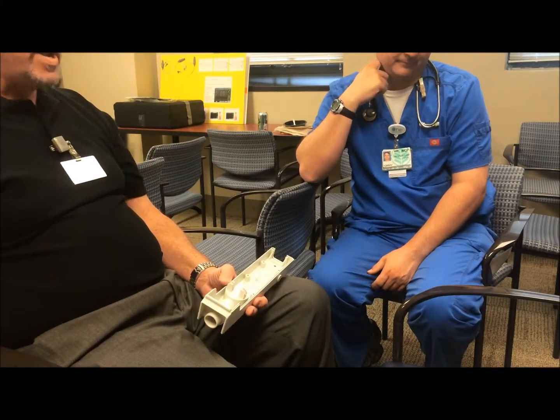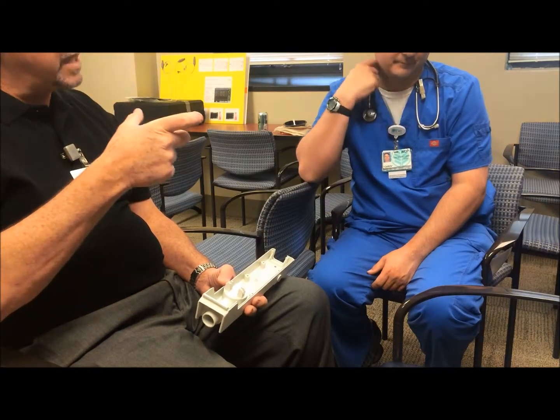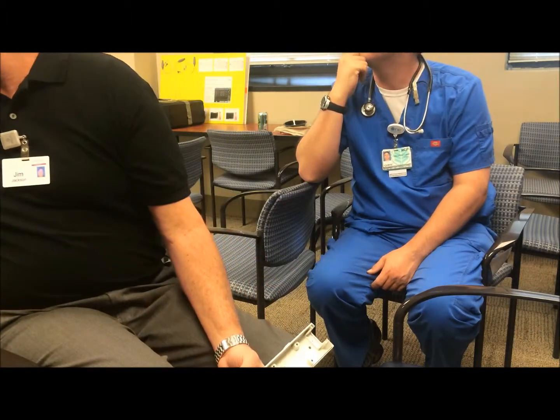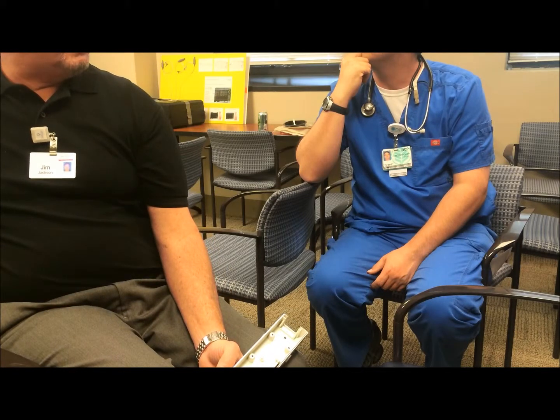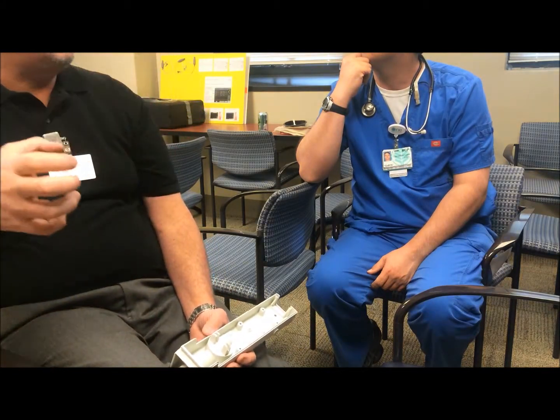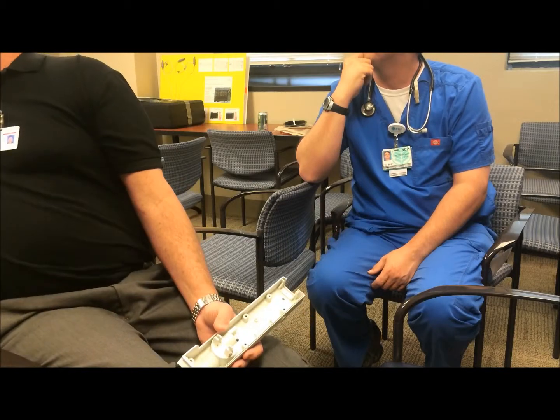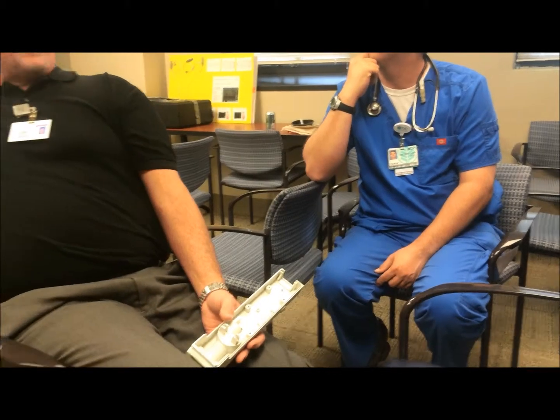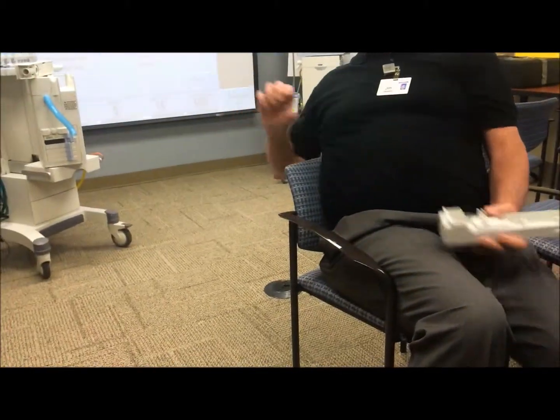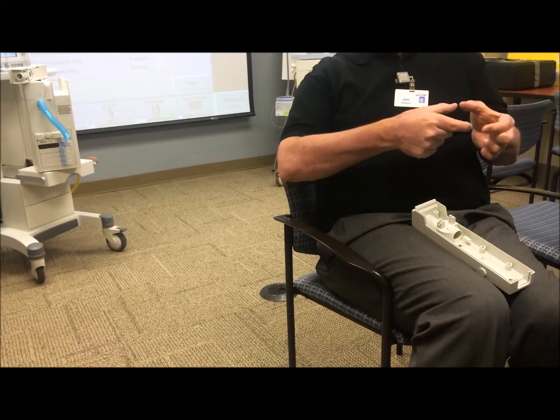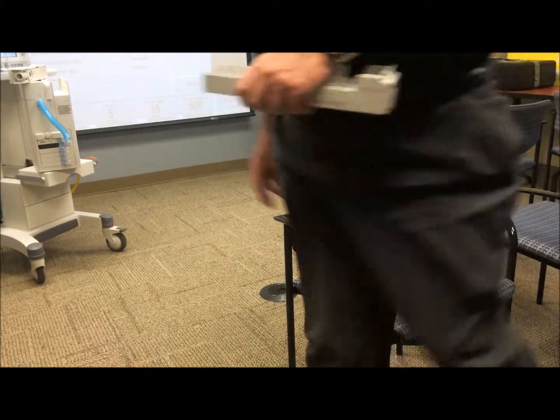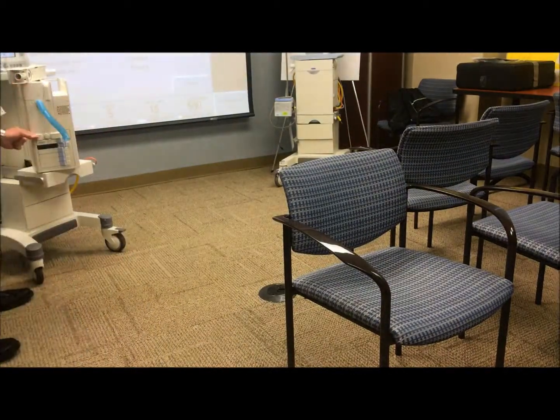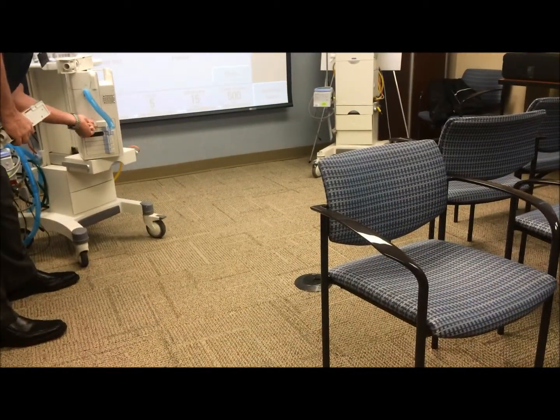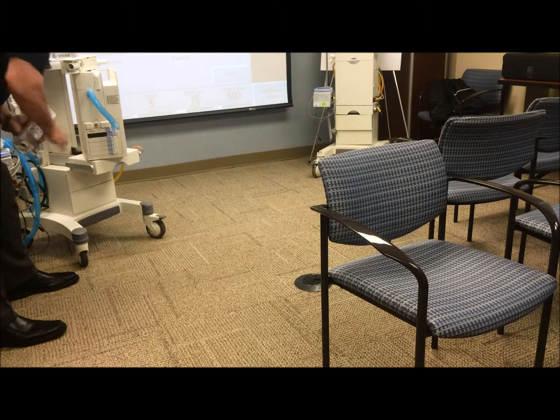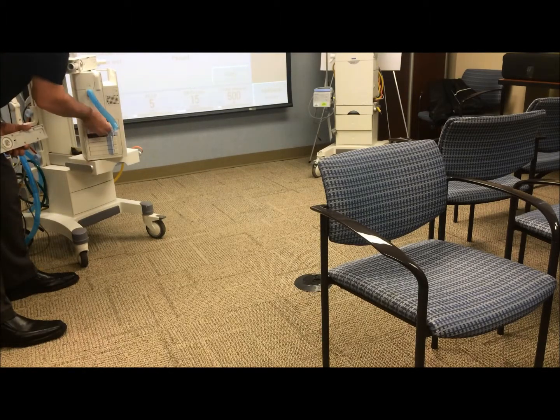But now we have the Aerogen nebulizers, and the Aerogen nebulizers are built into the ventilator, so you don't have to find the handheld units. It's built in right where that ultrasonic was, right above the battery bay there, and it comes out about this far from the side of the ventilator. It actually attaches to this port right here, goes in, and then there are two screws that hold it in there, but nothing is different about this. It just goes on there.